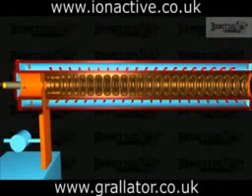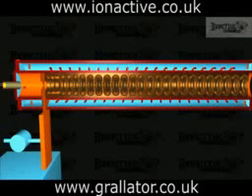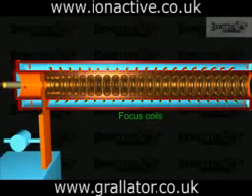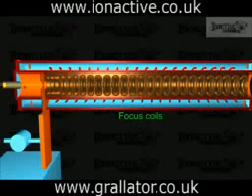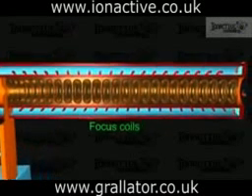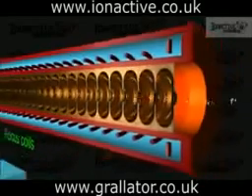For both accelerator types, the electrons are subject to forces during acceleration that tend to cause divergence of the beam. To control this, focus coils run along the length of the accelerator waveguide, preventing divergence and bringing the beam to the desired size at a point beyond the exit of the accelerator waveguide.